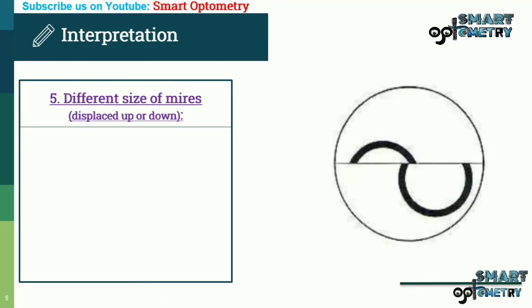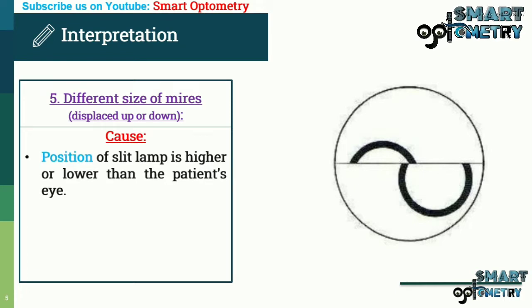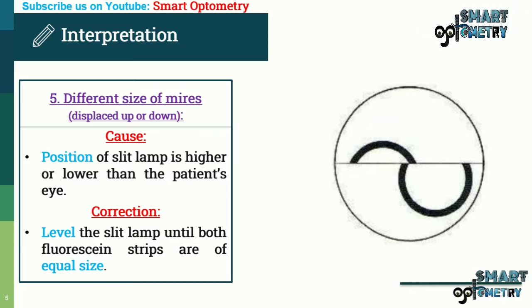Different size of mires displaced up or down. This is because the position of the slit lamp is higher or lower than the patient's eye. The correction is to level the slit lamp until both fluorescein strips are of equal size.